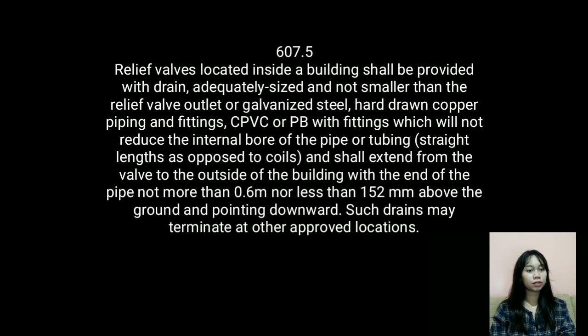Section 607.5: Relief valves located inside a building shall be provided with a drain adequately sized and not smaller than the relief valve outlet — of galvanized steel, hard-drawn copper piping and fittings, CPVC, or PB with fittings — which will not reduce the internal bore of the pipe or tubing. The drain shall extend from the valve to the outside of the building, with the end of the pipe not more than 0.6 meter nor less than 152 millimeters above the ground, pointing downward. Such drains may terminate at other approved locations.